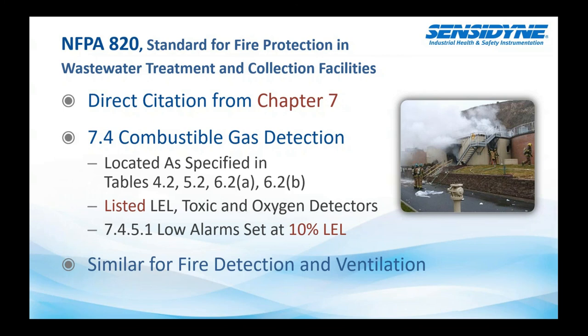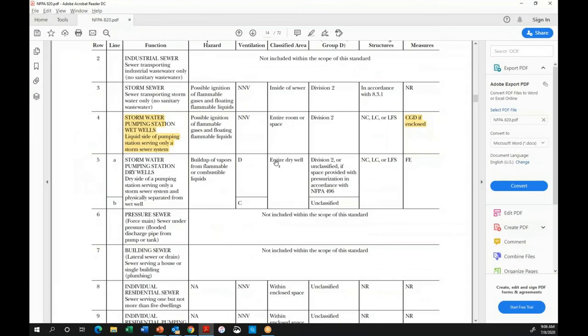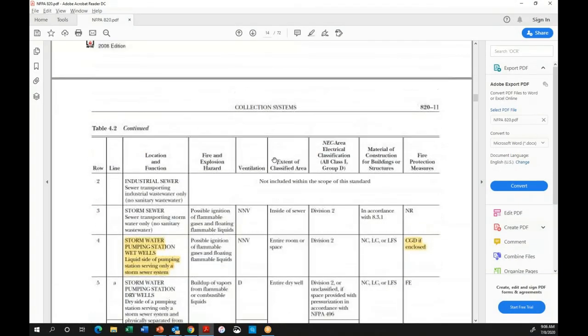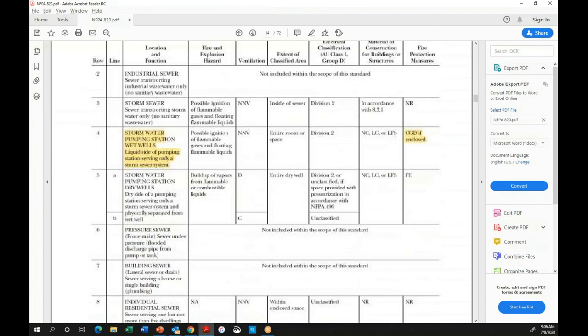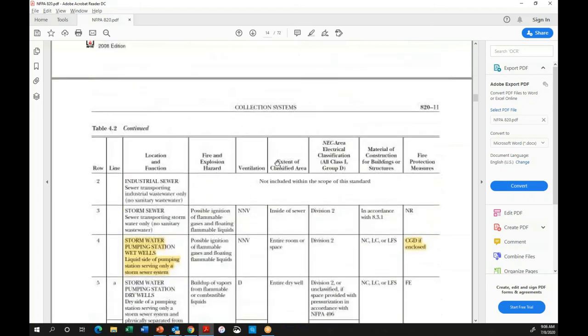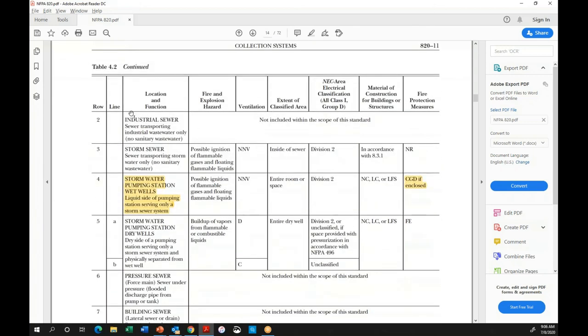And I wanted to show that code just quickly here. I'll pull that over and expand that. This is actually Chapter 7 in the NFPA standard. You can download this for free from the internet, or you can buy it from NFPA. But these tables, 4.2, 5.2, and 6.2, list all the different collection systems, the location and the function of that system, the fire and explosion hazard, ventilation, whether it's required or not, and you'll see these codes here. We'll talk about that a little bit more.